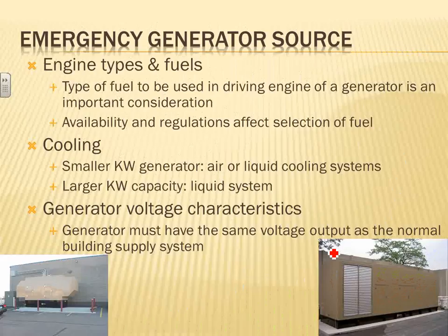The cooling system: you can use air to cool them, or you can use liquid to cool them. Depending upon the higher kW, they start cooling them by liquid. So the cooling system for the generator is a big deal. And the other thing, in terms of electrical characteristics for the generator, is the voltage that we run at. It has to match the voltage system of your building.